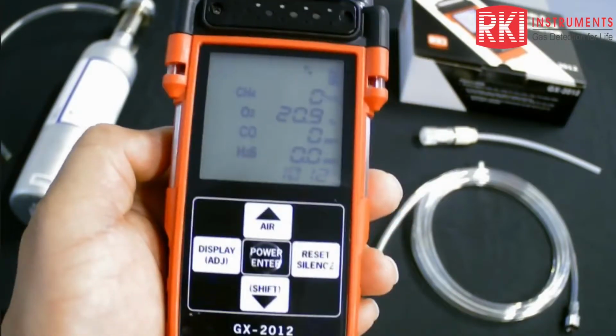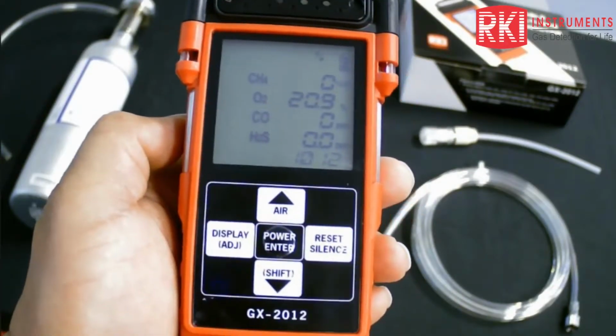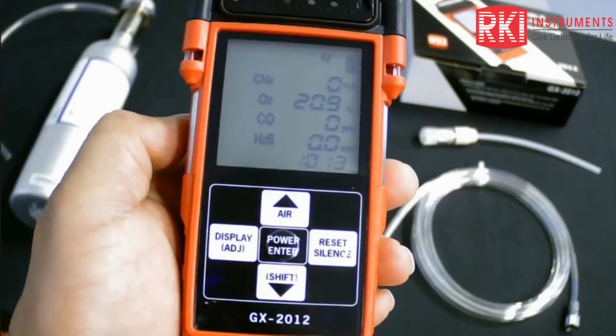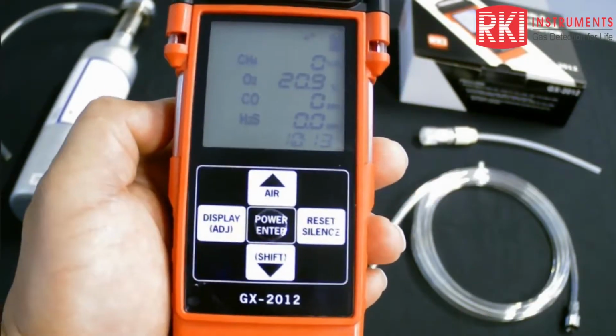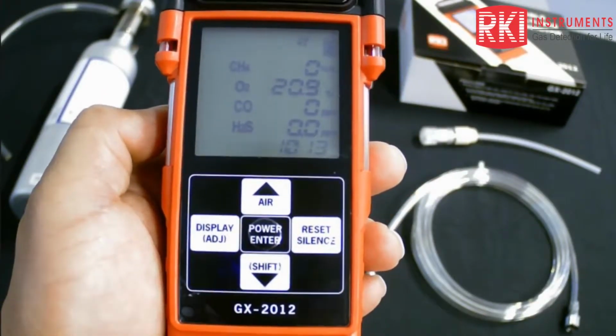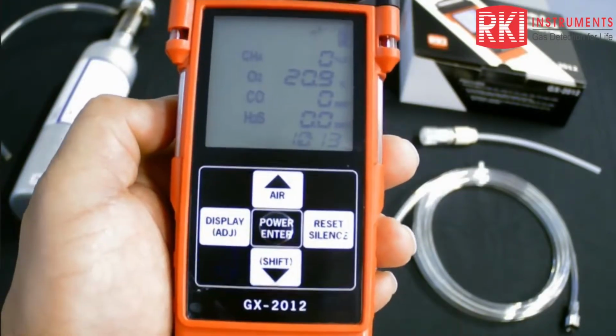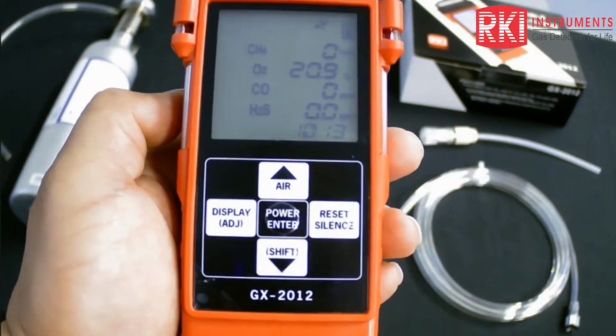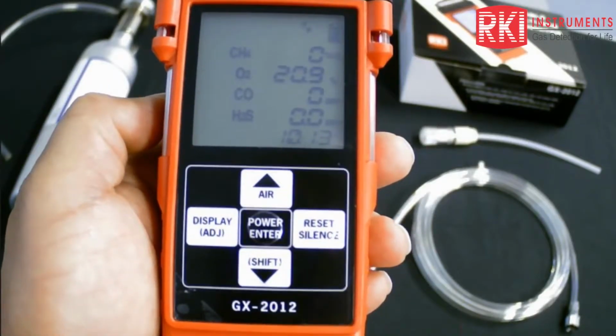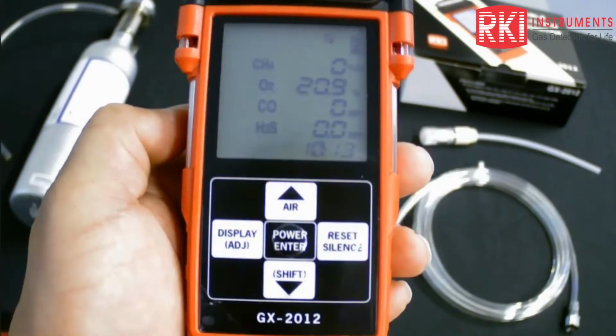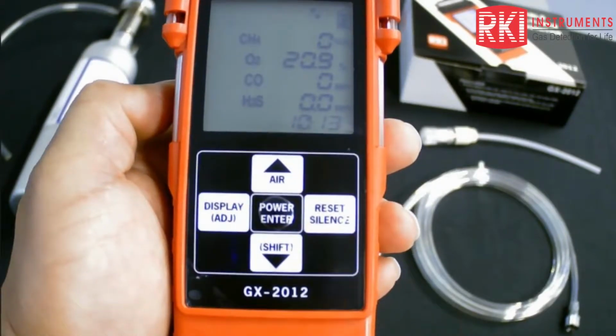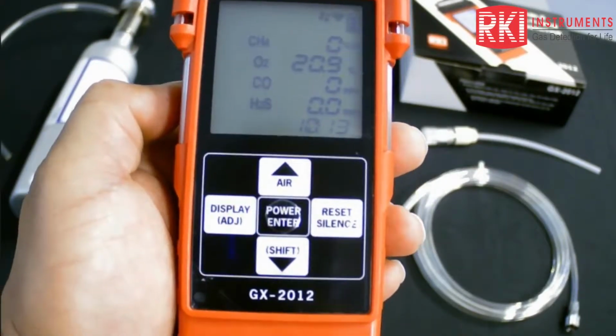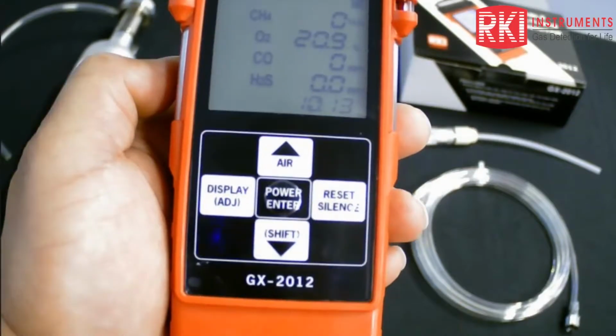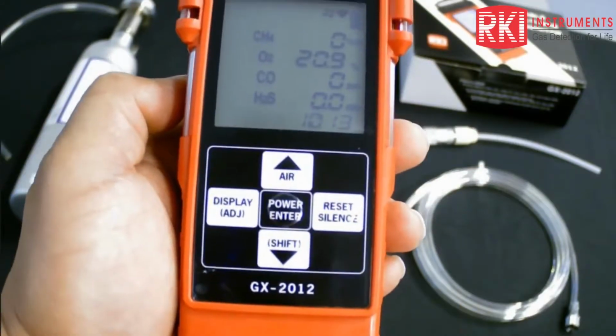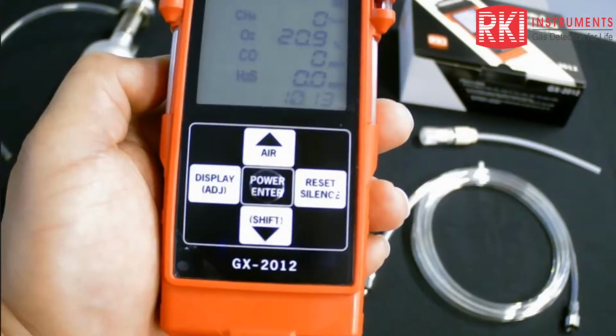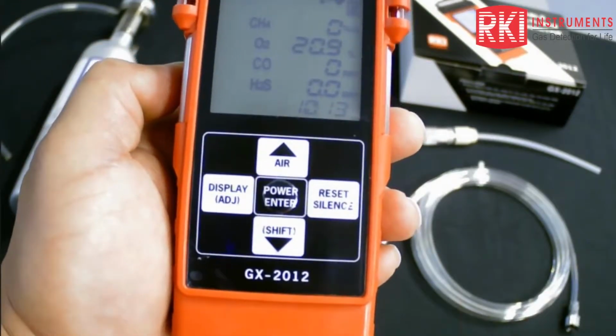Touching upon those concepts, the technologies that we use are what we call a catalytic combustion sensor or a hot wire sensor. It's almost like a light bulb in a sense that there's two filaments or two beads inside these sensors. Conceptually, you have a reference bead and an active bead or element. Basically, the reference is your baseline measurement. The active element basically measures the gas itself.